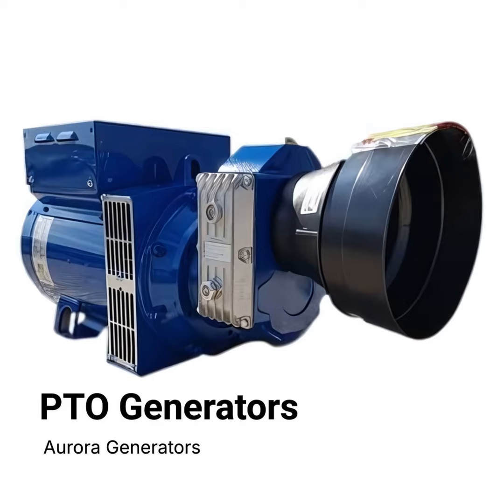Different places use different electricity standards, right? Voltage, frequency. How do manufacturers handle that? That's a huge consideration. Companies like Mecc Alte, and it's pronounced Mecalte. Got it. They design their alternators to be flexible. They use different winding configurations inside the stator to match regional needs. So one basic design might be adapted for, say, Europe versus North America. Precisely. You might configure it for 400 volts at 50 hertz, common in Europe, or maybe 480 volts at 60 hertz for North America, among other standards.